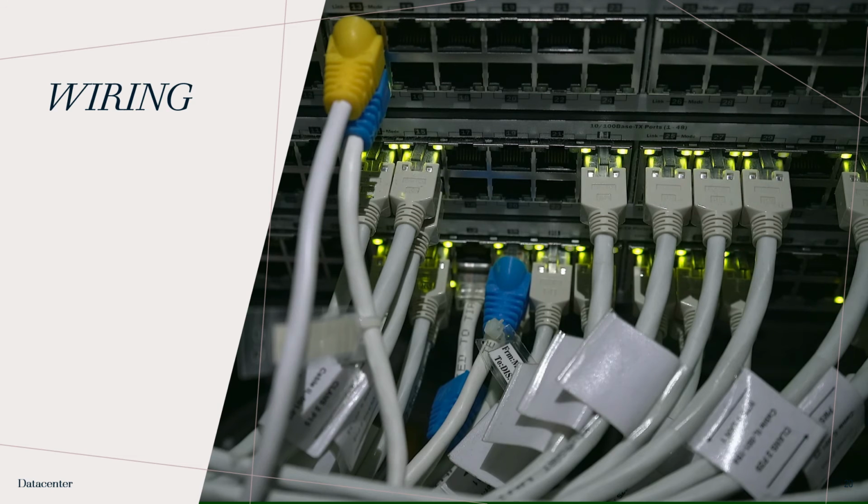Organization best practices are to run cables to the side of the server rack to ease adding or removing servers from the shelf. Bundle cables together to connect to the next piece of hardware, down to the floor in data centers with raised floors, or up to the ceiling in data centers with wiring that runs through the ceiling. Label cables securely on each end. This labeling process enables us to conveniently locate cables for testing or repair, install new equipment, or remove extra cables after equipment has been removed or upgraded, which saves time and money.